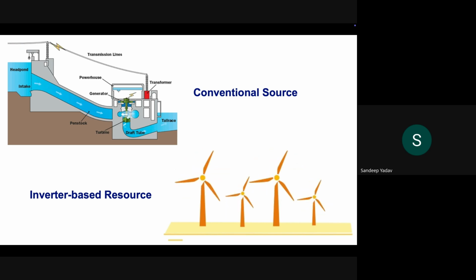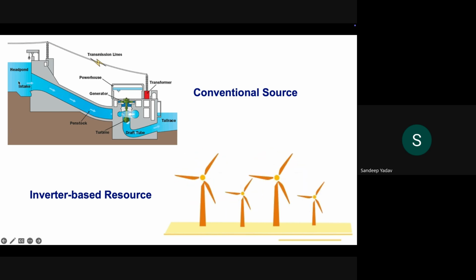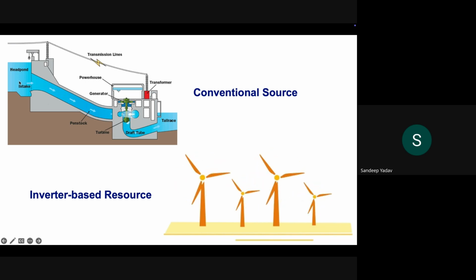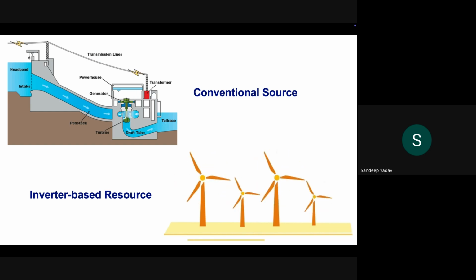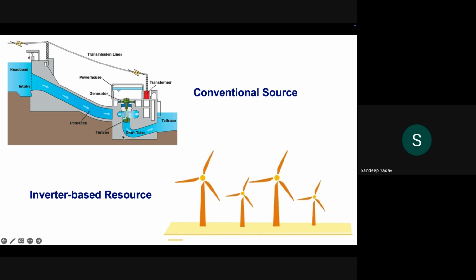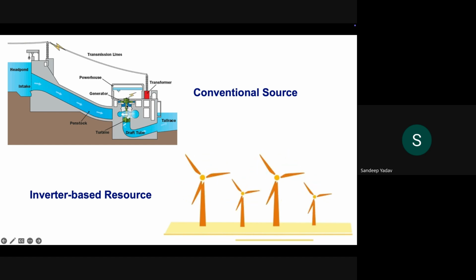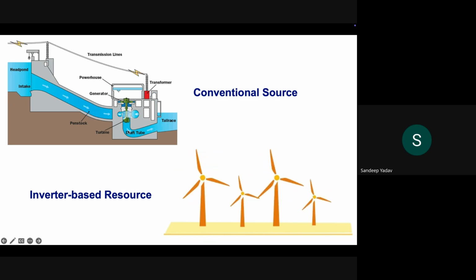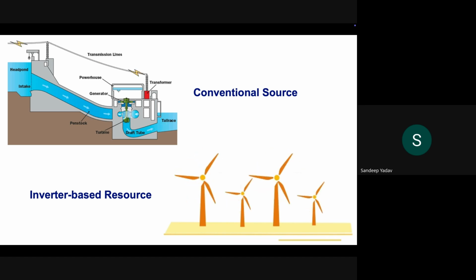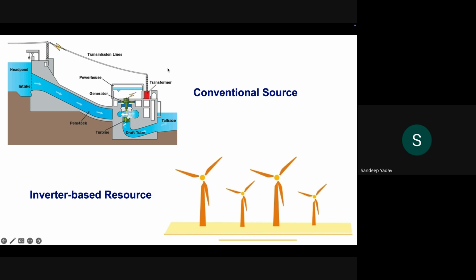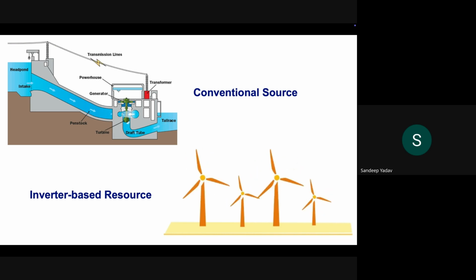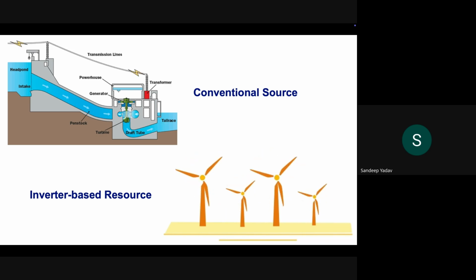If you look at a conventional source, the energy medium, which is usually steam generated from coal or gas, runs a large rotating mass, which is the rotor. The kinetic energy is transferred from the rotor in the form of electromagnetics to the stator, the alternator winding. It is converted to electrical energy, and then all the generators connected in parallel feed the load. So technically, the machines have a large inertia in the form of the large rotating mass. The bigger the machine, the more mass it has, and the higher the inertia.